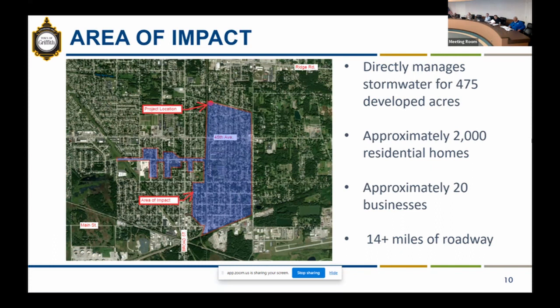Indirectly, it handles another 100 to 200 acres conservatively. As Katie Marsh level rises, most of the town's storm sewer on the south path gravity-discharges through flap gates and duck bills. When Katie Marsh is up, those systems back-feed into this stormwater pump station. So on high flow, there is additional acreage of land feeding into this pump station that will be missed on heavy stormwater events.